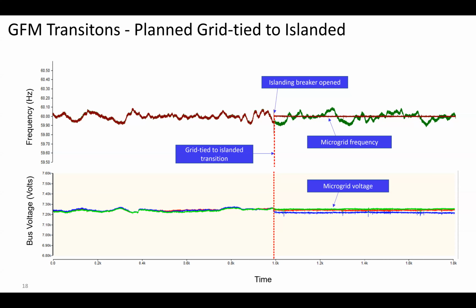So this first graph here is frequency versus time. The maroon is the KIUC grid frequency, while the PMRF microgrid is grid tied. We initiated a grid tied to islanded transition, moving from grid connected to a microgrid mode, in other words. It's an automated sequence that's been co-developed between AES and KIUC. So we initiate the sequence, move through the automated transition, and the islanding breaker is opened here. And what you'll see is, after we disconnect from the grid with the PMRF naval facility loads, the PMRF microgrid holds its frequency pretty stable and continues powering the PMRF loads.